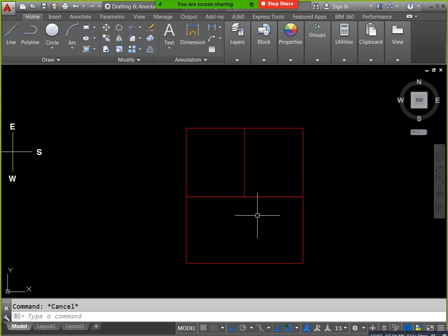But you will take this line and this line. Here you have a horizontal line and this vertical line. These 3 walls we consider as the inner walls. We have 2 more conditions here. For example, this is an AC room, meaning conditioned space. This is a non-AC room, meaning unconditioned space. AC, non-AC, this is a partition. Why is this a partition? In the non-AC room we have high temperature, right? In the AC room we have low temperature, so this is also one of the heat transfer ways for this room.